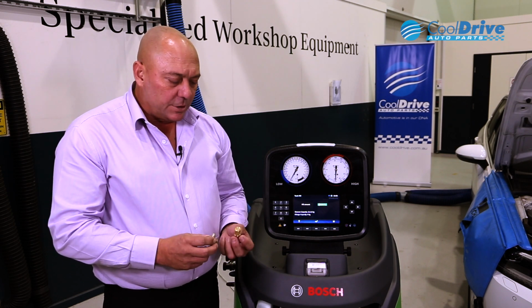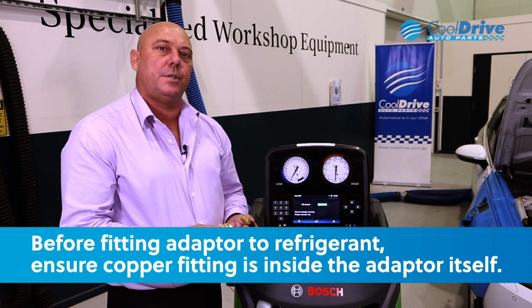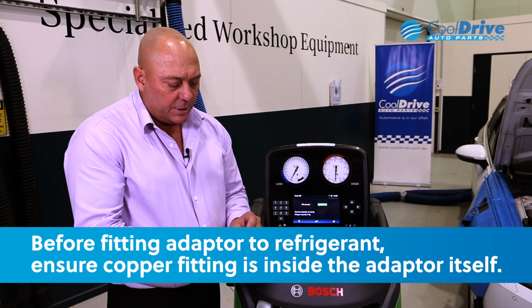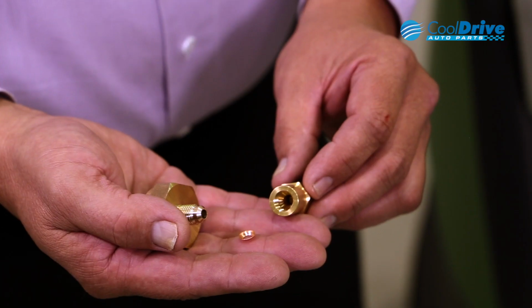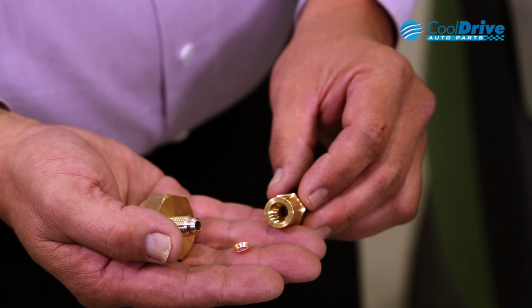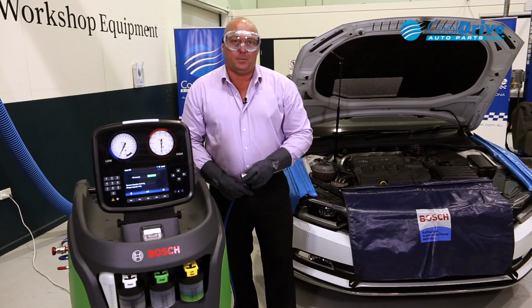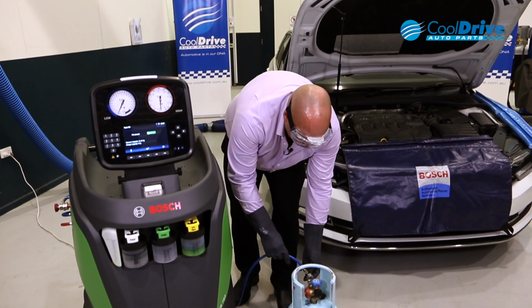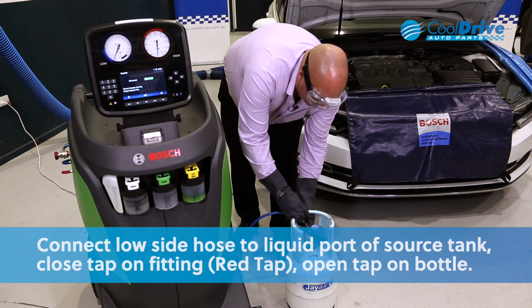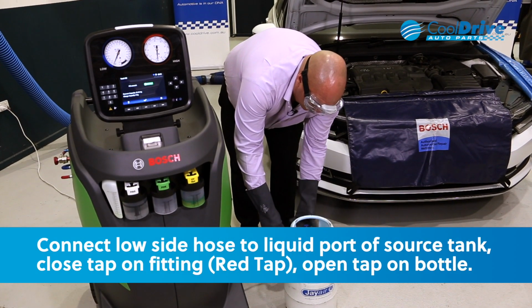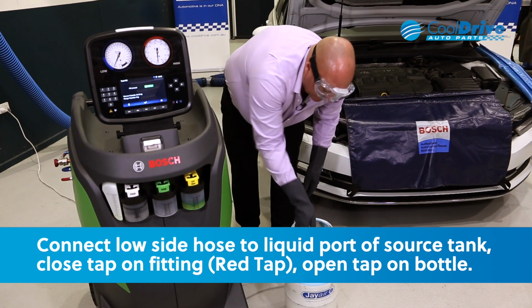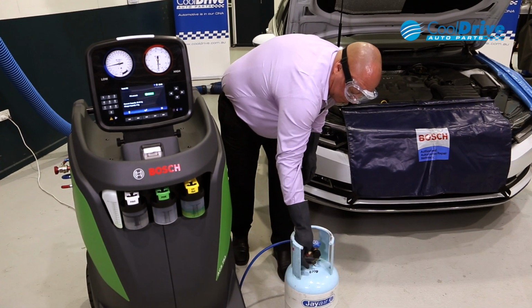It's worth noting, just ensure before fitting the adapters to your refrigerant that the copper washer is actually fitted inside the adapter itself. To fill the internal bottle, we attach the low side hose to the liquid port of our source tank, close the tap on the fitting, and then open the tap on the bottle.